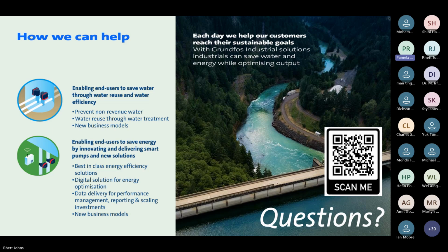And then another question. In the wastewater treatment, we do a lot of like-for-like replacement, where there's often space restrictions when retrofitting. So it's not feasible to install an additional pump. What is the best approach to selecting the new pumps in that situation? So wastewater systems, the best method in order to reselect your pumps would be to really get an understanding of where they are operating. So what we do is we do that energy consumption monitoring, we do flow monitoring on the systems. We come in and we install that hardware on site, and we then monitor, maybe 2 weeks, depending on the complexity of the system, maybe 4 weeks, and we define then the flow classes of those systems.